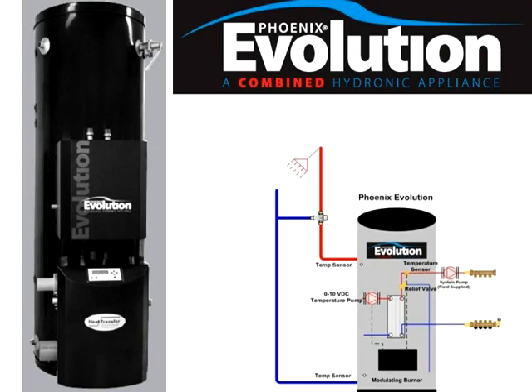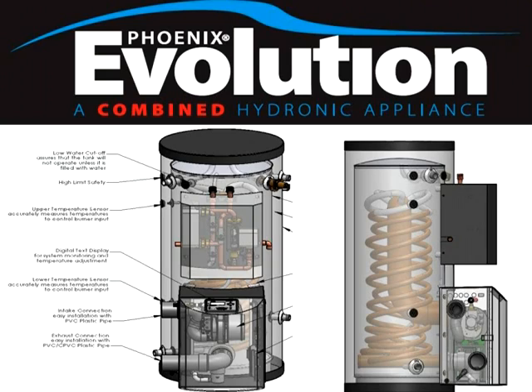Now notice that it does show radiant. We are introducing some low temperature baseboards soon, but you'll see that this unit does go up to 160 degree output. Now, just diagrammatically, we have the Phoenix, and then on the upper module here a braze plate heat exchanger with a variable speed control connected to it, a series of valves, a pressure relief valve, etc. That is there for the purpose of extracting heat from the tank into the heat exchanger, and then on the other side taking that heat and delivering it out to your hydronic system in a seamless way.